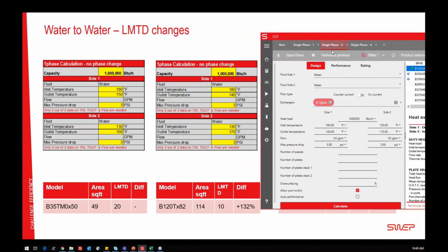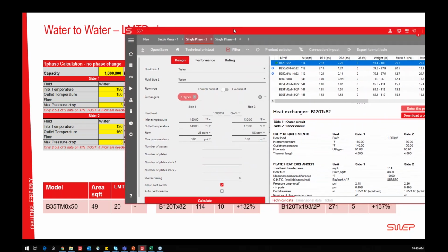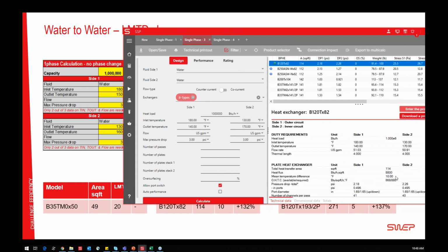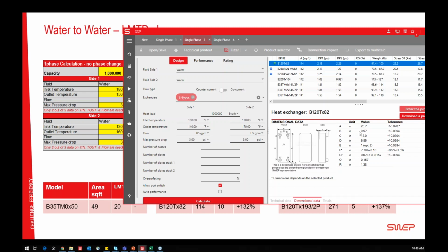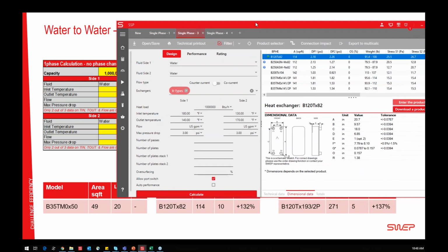Going back here. This is what we expected, because it's thermally short, and then the pressure drop will be the limiting factor. So that's what we got. Perfect. Let's look at the second one. It's exactly the same data, except that the temperatures have come a little bit closer. So 150 became 140, 160 became 170. And what do we see here? We see that the LMTD has gone down from 20 to 10. We got 10 Fahrenheit closer. B is the same width, so it's still about 10 inches wide, but the height has now gone up from 16 to 21 inches. So it's thermally longer, needs a taller heat exchanger and more heat surface area, as we see as well.